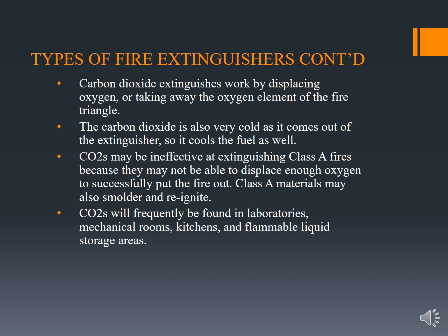CO2s may be ineffective at extinguishing Class A fires because they might not be able to displace enough oxygen to successfully put the fire out. And Class A materials may also smolder and re-ignite. The CO2s will frequently be found in laboratories, mechanical rooms, kitchens, and flammable liquid storage areas.